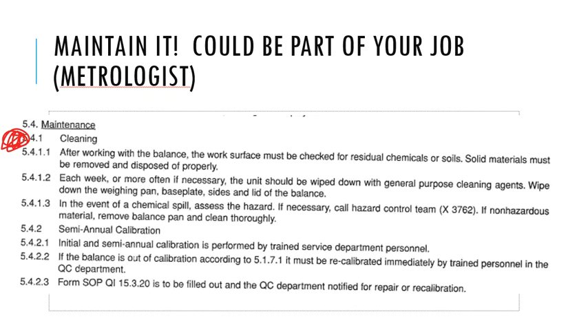So as far as the analytical balance goes, you want to make sure that the inside of the balance pan stays completely clean. Wipe it down, sweep off the powders. You want to make sure that everything in that chamber doesn't have any residue or any kind of sticky liquid that can eat away some of the metal or that can stay behind, because that's going to be the number one problem, just messiness of you weighing out things.